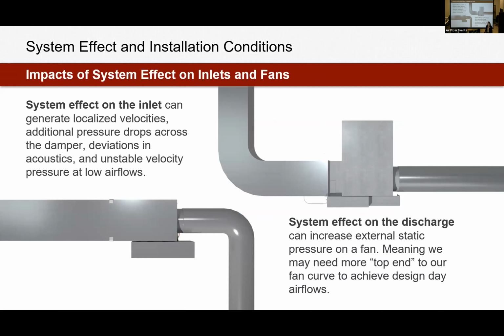So on the inlet, just like what we saw, if we've got tight elbows on inlets, maybe we have sagging flex duct on inlets. On just that particular box, we're going to see localized velocities that will ultimately result in poor airflow measurement and control. So a crossflow sensor can compensate a little bit better for this, but if you've got another type of sensor, it's going to be picking up really high velocities on one side of the duct, but it'll be reading nothing on the other side, and it's not going to be very good at compensating for that.